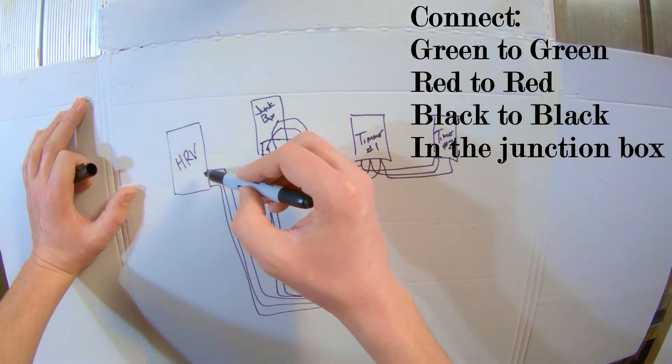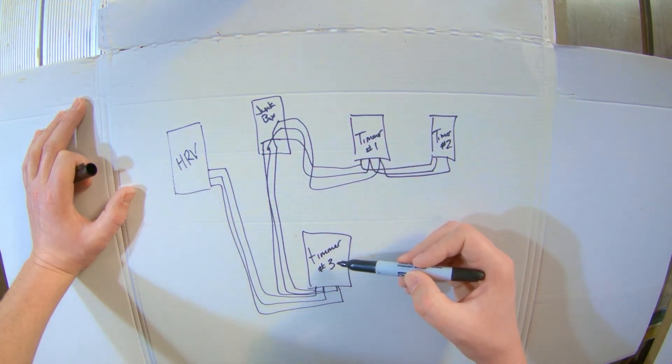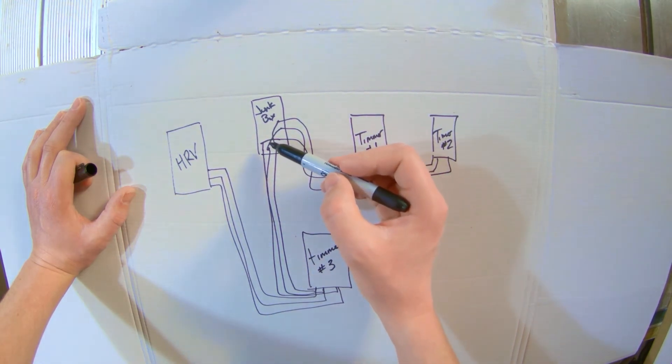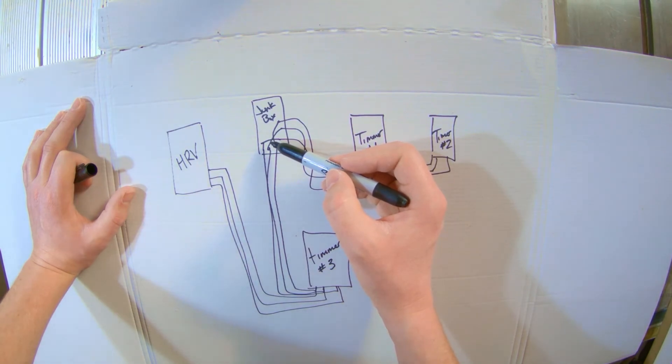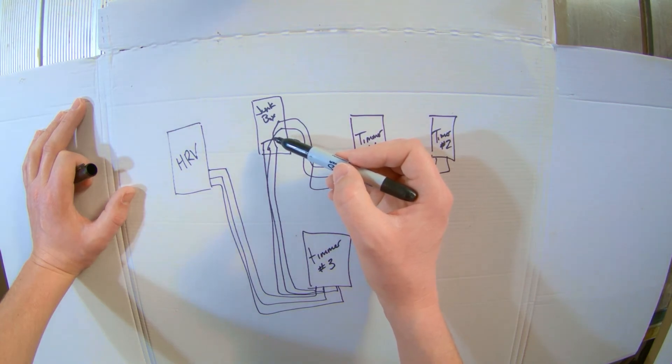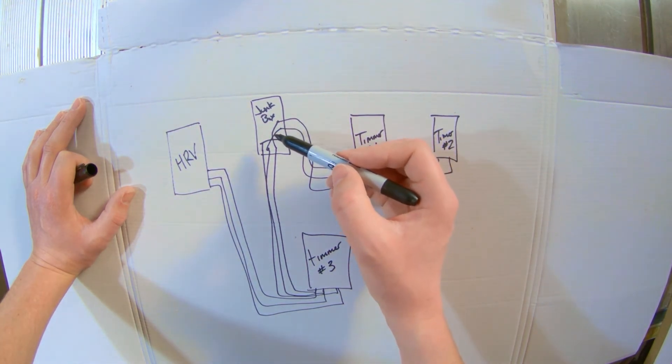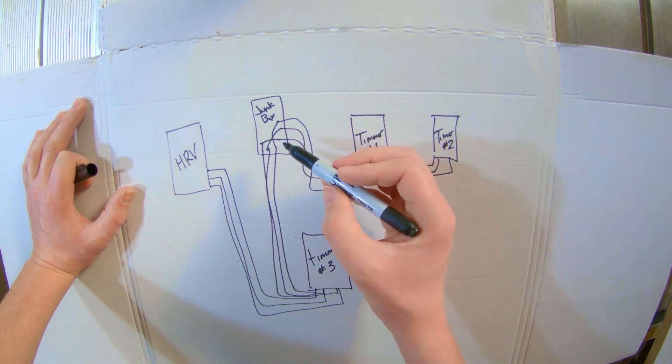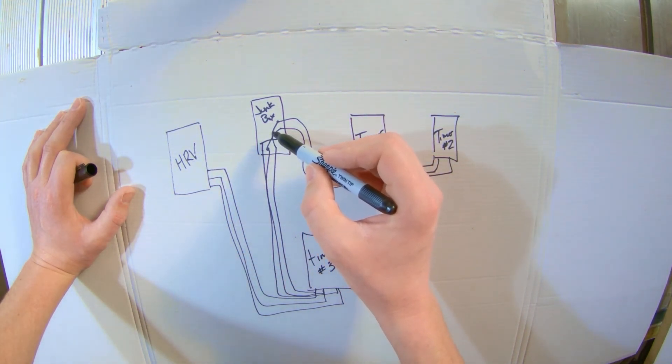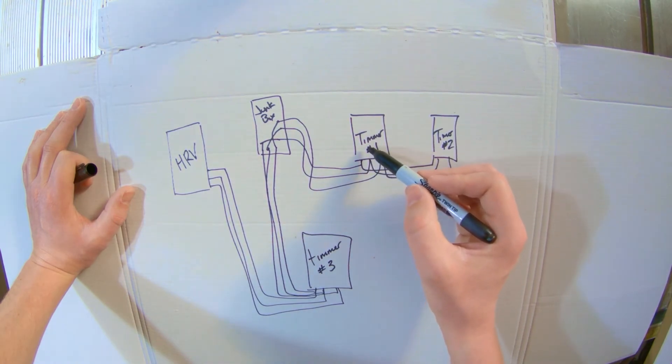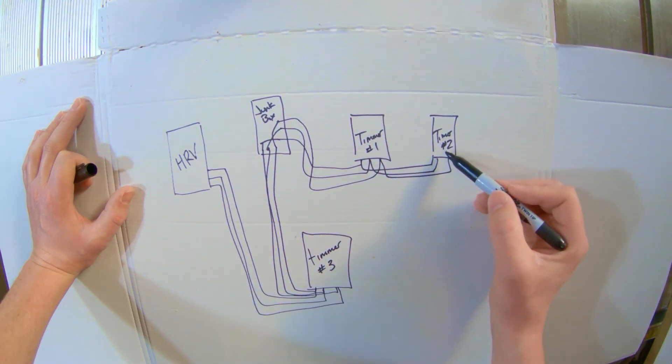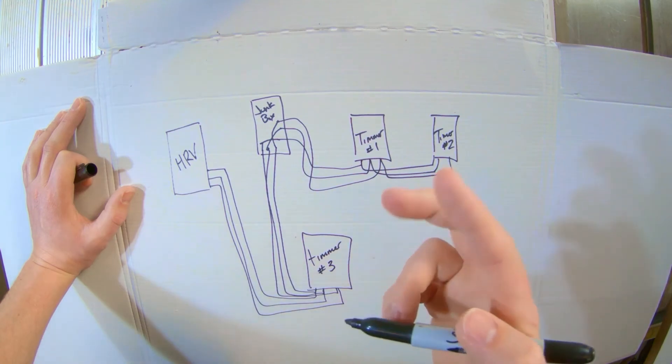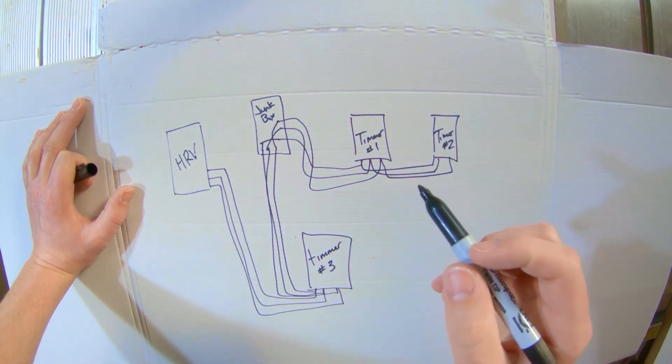And now you've created this circuit coming out of the HRV to timer three, back to this junction box in your mechanical room that's accessible at all times. Because anytime you're joining wires, it needs to be in a junction box that's accessible at any time. So surface mounting that in your mechanical room is pretty convenient. You can put it right next to your HRV. And then you've got wires going to timer one and then to timer two.